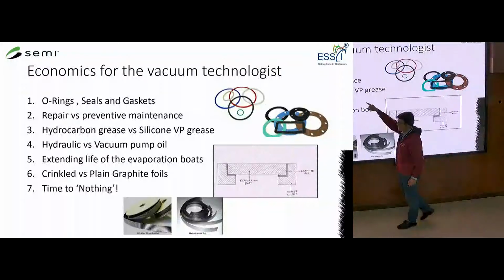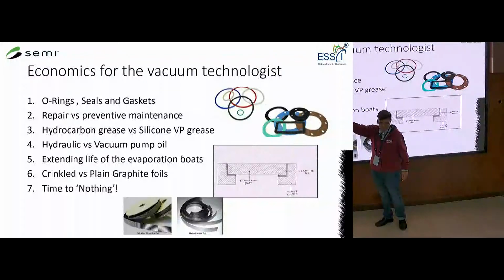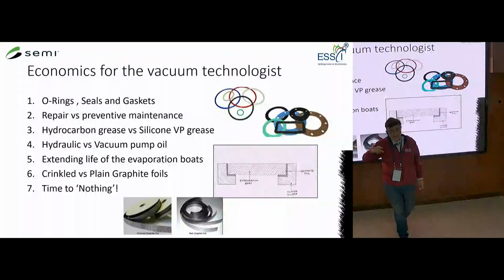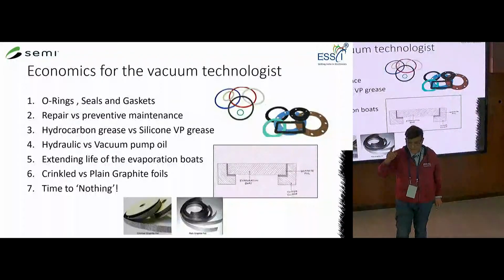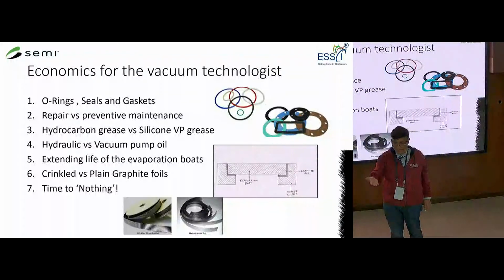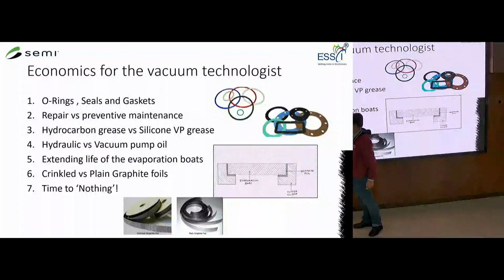Tip 2 is you can play between repair and preventive maintenance, but really the right thing is to have preventive maintenance, because then you go for a predictable and more efficient execution of your process of creating the ultra high vacuums. There is always this situation where you can have different types of greases to do the sealing of your mechanical points. Would you use a hydrocarbon grease? Would you use a silicone grease?